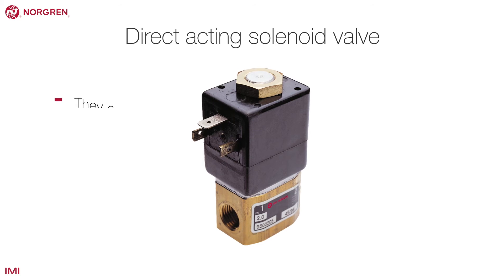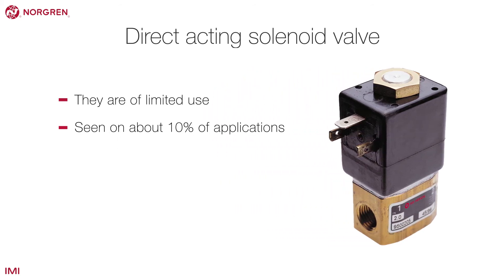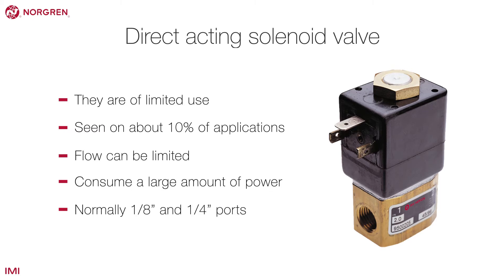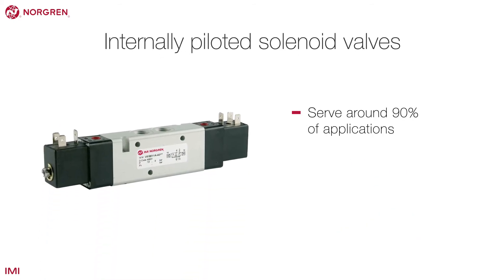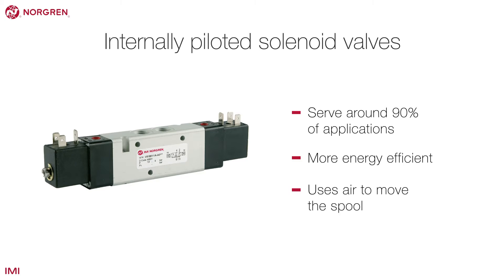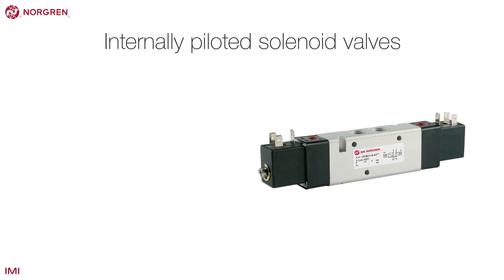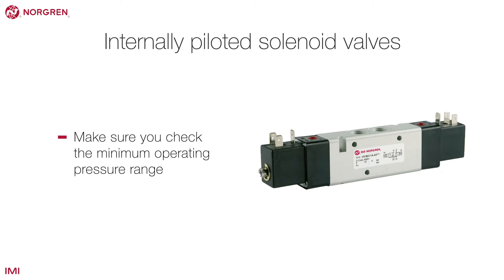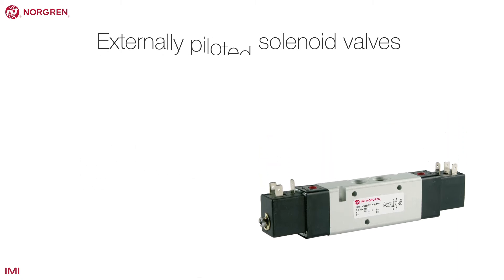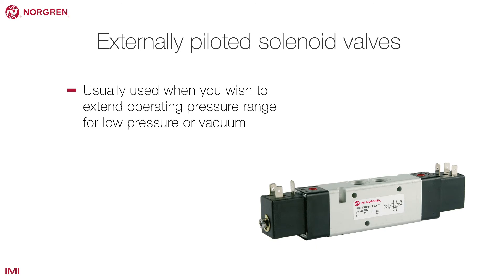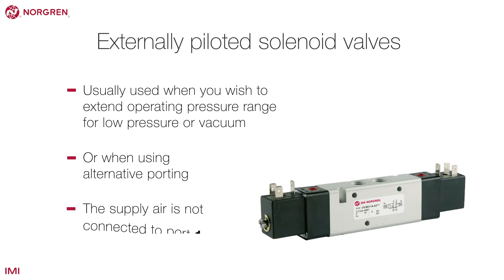Direct acting solenoid valves are of limited use and are seen on about 10% of applications, mainly because flow can be limited and they consume a large amount of electrical power. Internally piloted solenoid valves serve around 90% of applications — this is by far the most common type and is much more energy efficient, using air to move the spool across and change the position of the valve. When selecting a valve, check the minimum operating pressure range. An external pilot is usually used when you wish to extend the operating pressure range for low pressure or vacuum, or when using alternative porting where the supply air is not connected to port 1.